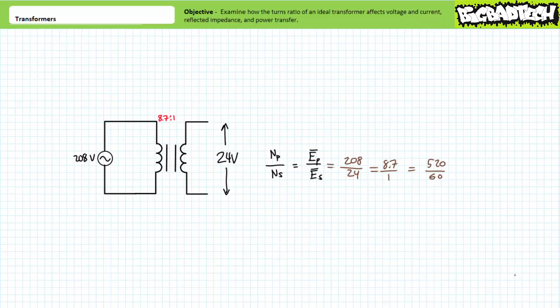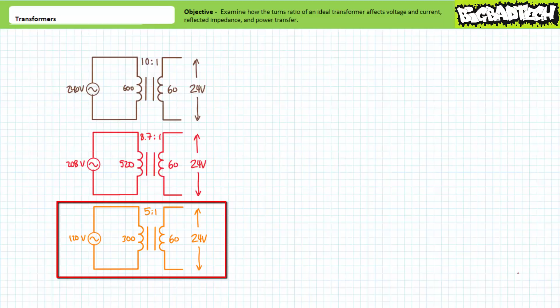3 different primary voltage levels might necessitate 3 totally different transformers, each with their own specific turns ratio. One with a 10:1 ratio for 240 volt applications, one with an 8.7:1 turns ratio for 208 volt applications, and yet another one with a 5:1 turns ratio for 120 volt applications. However, a simple modification allows a single transformer to perform these different roles. Consider a multi-tap transformer, it being a transformer with different access points or taps on a single winding.